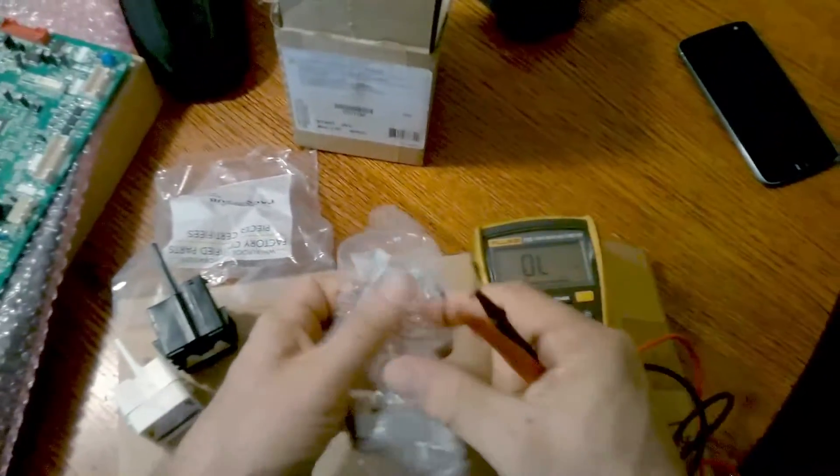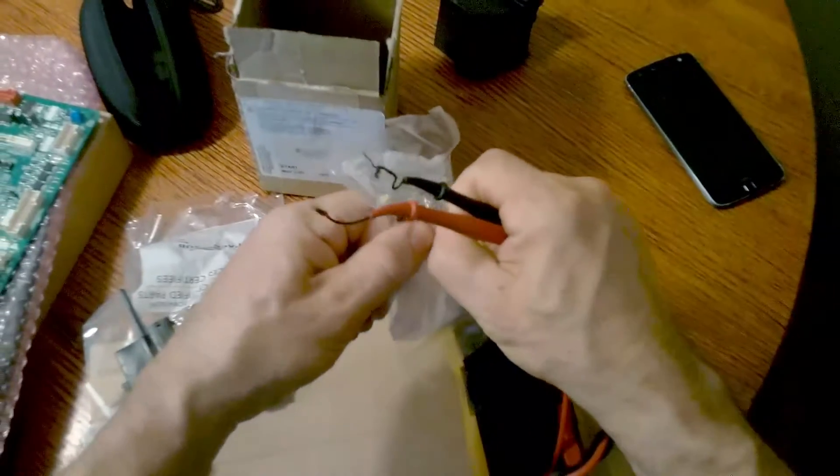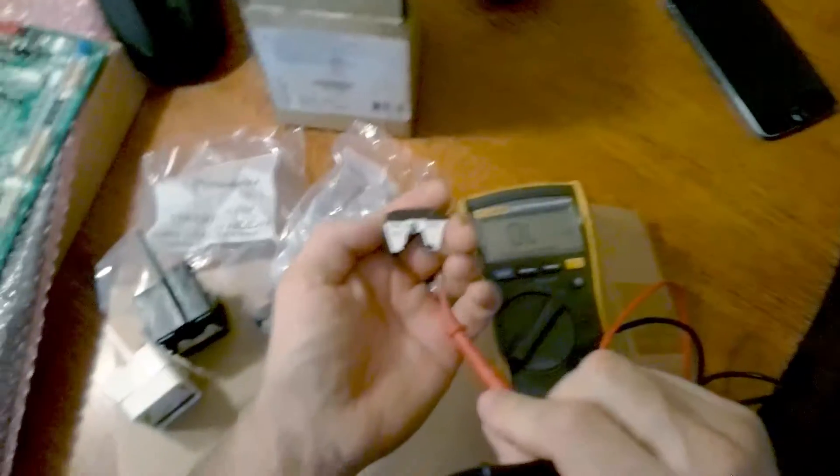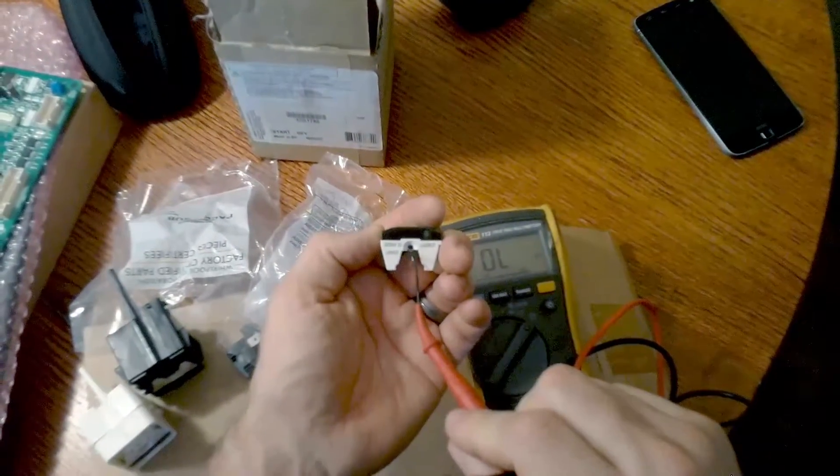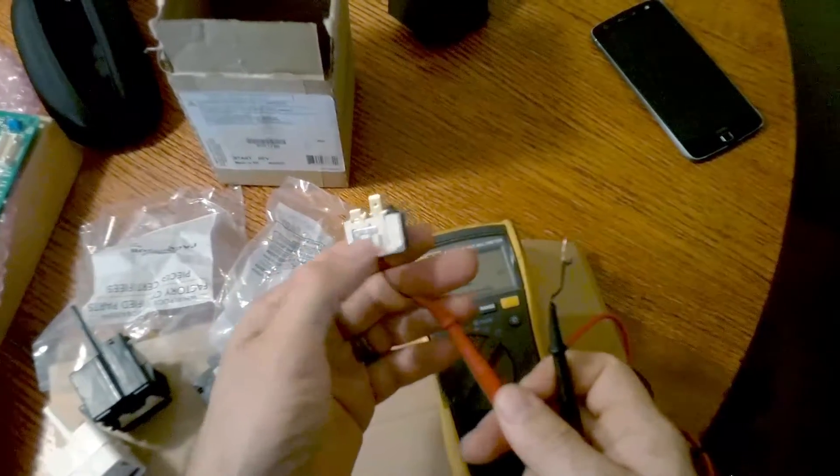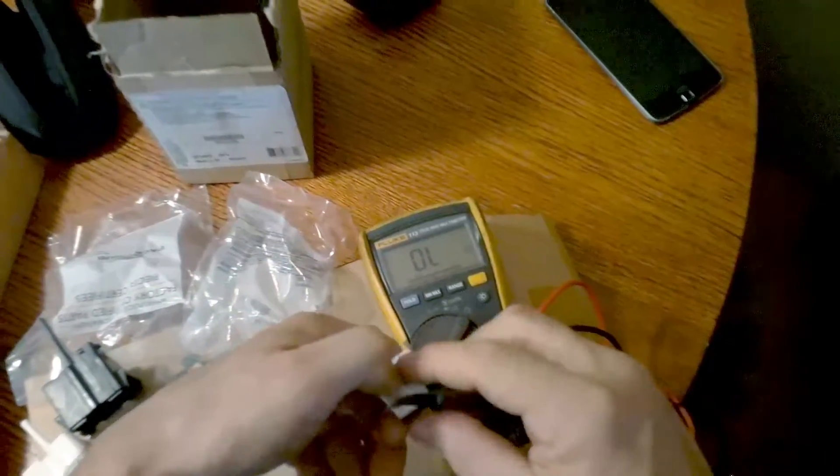And this is your overload. This is where the main common power comes in to start the compressor. They usually never go bad, but if you want to test it, you put your multimeter in the top pin and then the back pin.